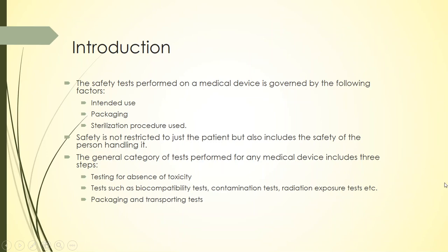So the safety tests performed on a medical device are governed by the intended use, right? Where exactly are you planning to use the device, or where exactly does the manufacturer say that this device is supposed to be used? That matters. The packaging matters, because you should pack it in such a way that the device is a sterilized product, and then when you open it, the sterility shouldn't get compromised. It shouldn't be such that you open it and then you have to put your bare fingers inside the packet, and that would jeopardize the sterility. The packaging should be such that the sterility doesn't get compromised, and then the sterilization procedure used as well.